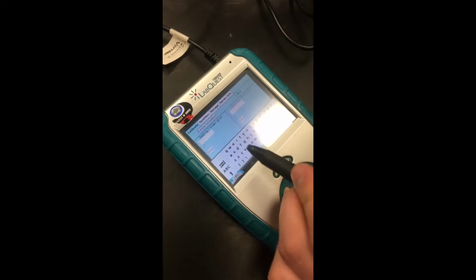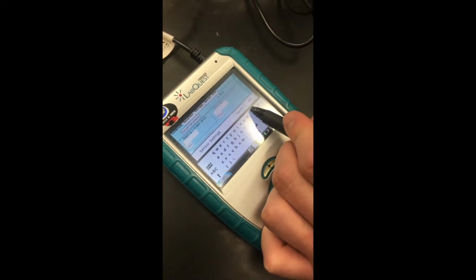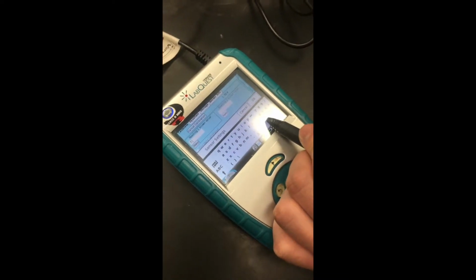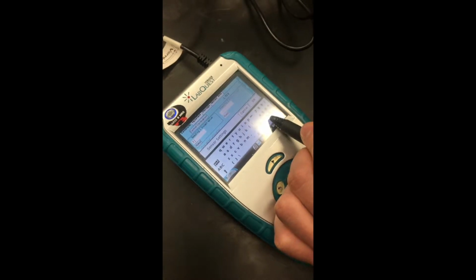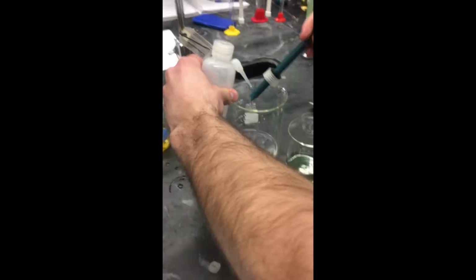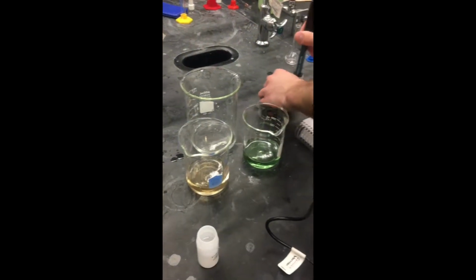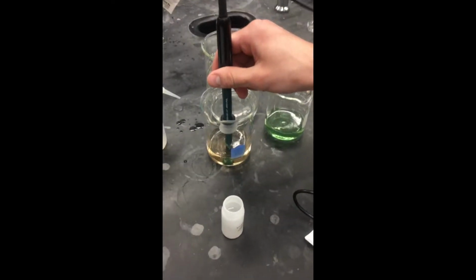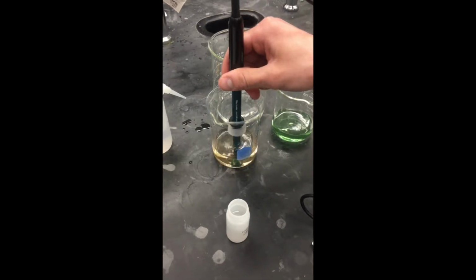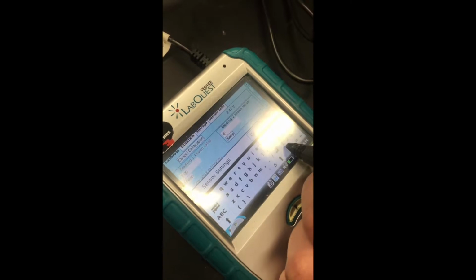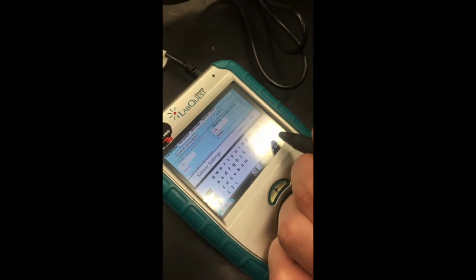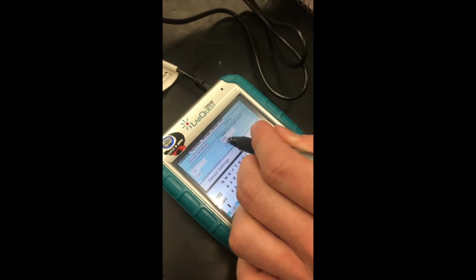So he's going to hit calibration, and then he's going to input 7.00 for calibration. And then he's going to hit keep, rinse the probe again with distilled water, and again rinse the probe off, and put the probe back in a buffer of 4 pH. And once that voltage at the top stabilizes, he's going to input 4.0 and hit keep.